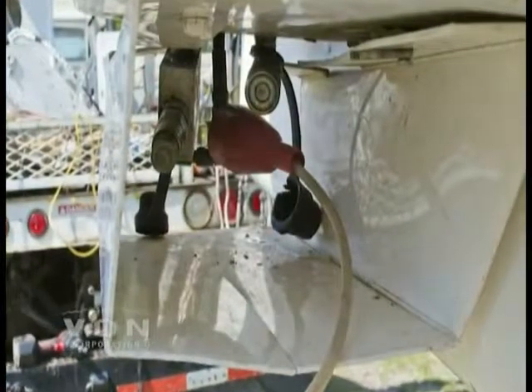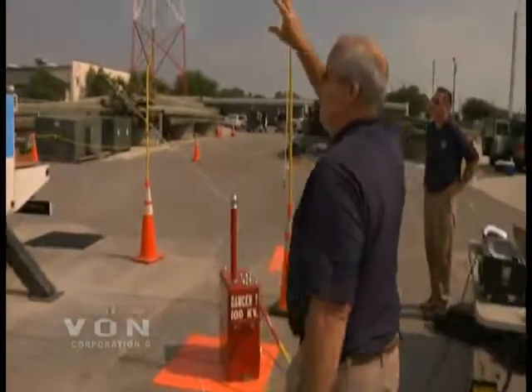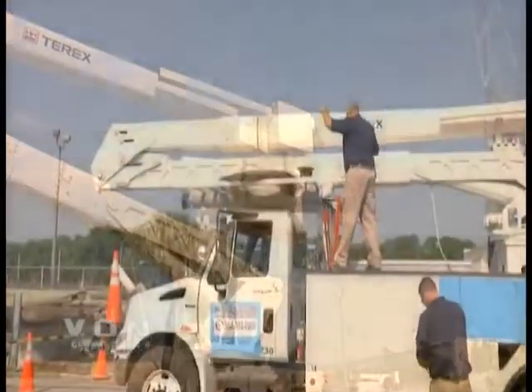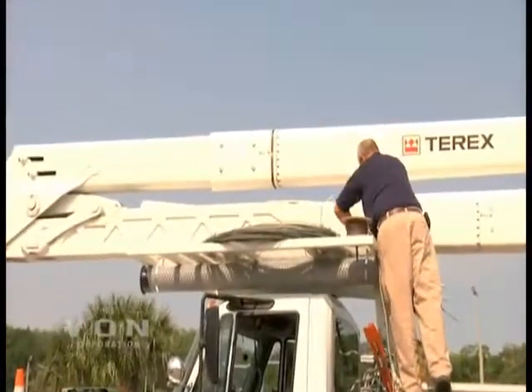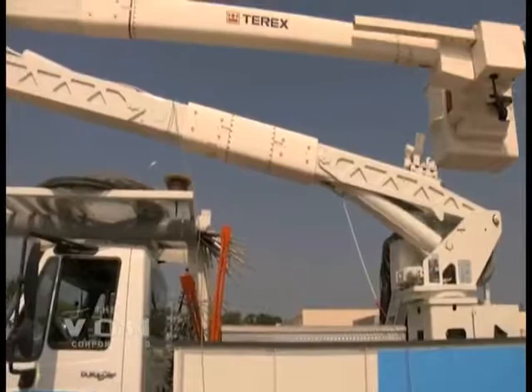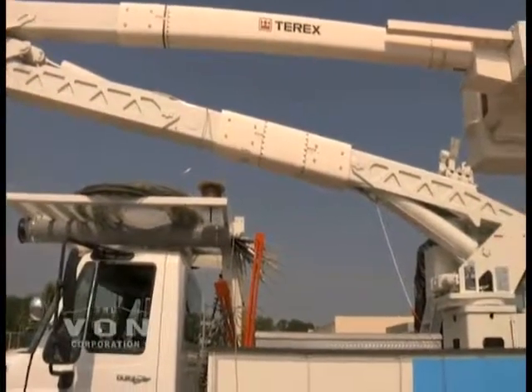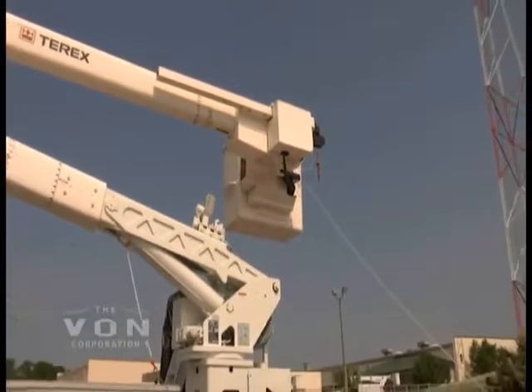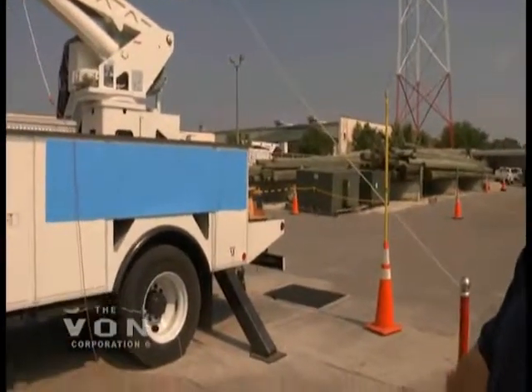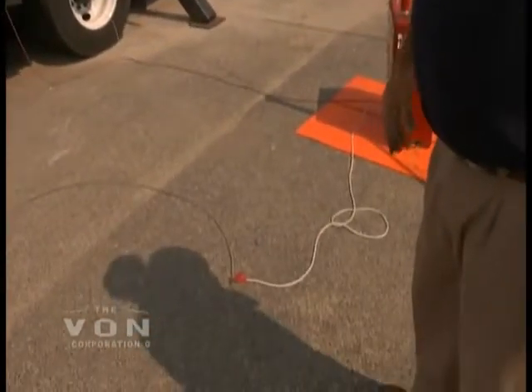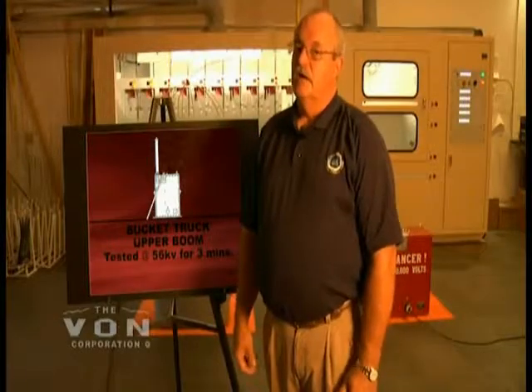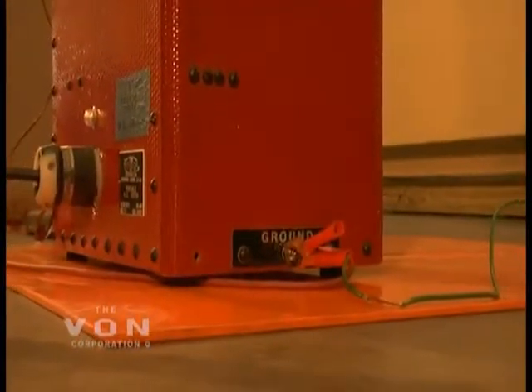We have connected the upper boom with the three-way high voltage lead. We have connected the lower boom chassis, where we're going to test it, with our single high voltage lead. And we have grounded the lower part of the boom. We're going to test the upper boom, and when we get through testing the upper boom, without moving this unit, without doing anything else, we're going to disconnect this lead and energize this next lead to test the lower chassis in just a matter of a few minutes, so that the test can be run without a lot of movement of the trucks. When testing the upper boom, ensure that you ground the knuckle of the upper boom along with the truck body to the ground on the red test unit.